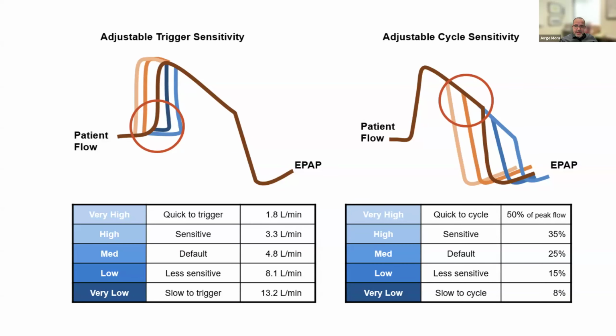The cycle, on the other hand, you would like them to cycle early to decrease that inspiratory time. So you will use a high sensitivity in these patients. And again, remember, whenever you see a percentage in cycling, what you're seeing is what is left. What I mean by this is if you set most of these devices on 20% or 50%, whatever you see there, 20% cycling means that the device will cycle once the maximum flow has decreased by 80% and 20% is left. It's counterintuitive sometimes, but that's the way it is.